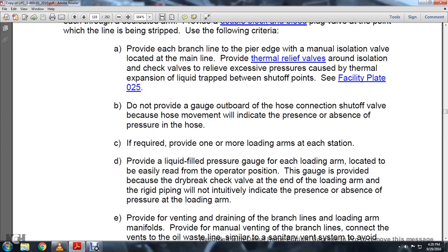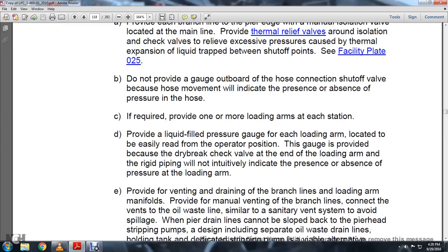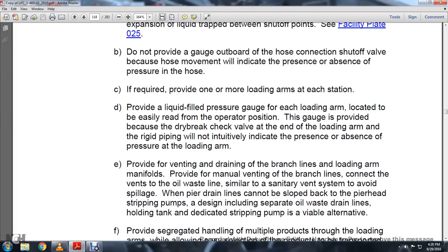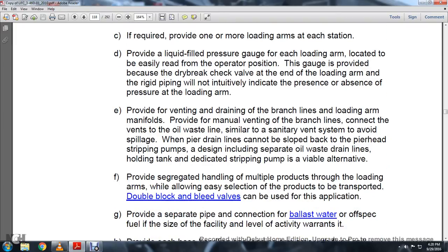If required, provide only one or more loading arms at each station. Provide a liquid-filled pressure gauge for each loading arm, located where it is easily read from the operating position. The gauge is provided because the dry break check valve at the end of the loading arm and the rigid piping will not otherwise indicate the presence or absence of pressure at the loading arm.